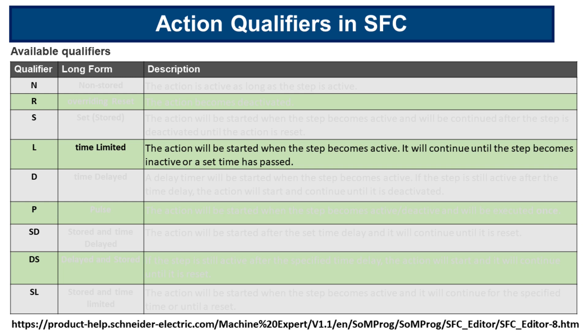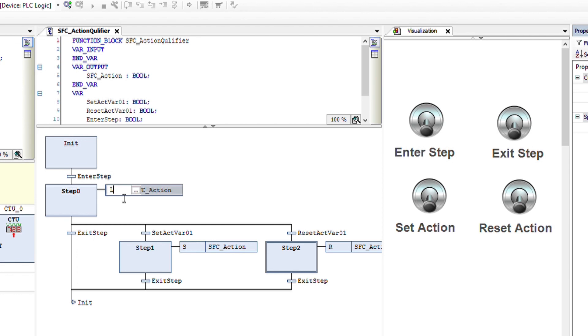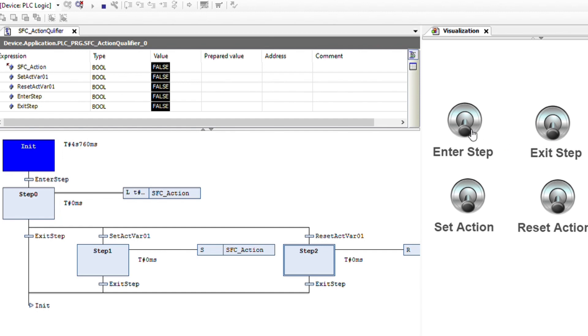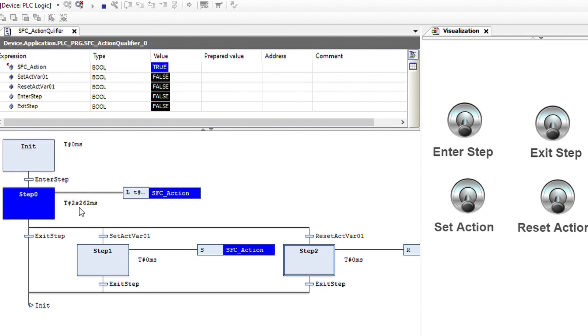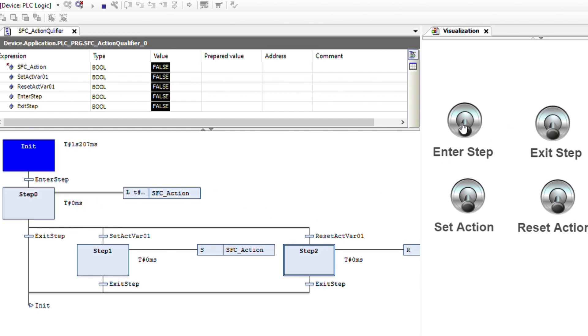The next qualifier is L, which stands for time limited. The action will be started when the step becomes active; it will continue until the step becomes inactive or a set time has passed. I'm going to change the qualifier to L and specify a time value — T#3s, three seconds. We are in the init step. If I press enter step, we enter into the step. The action becomes true and it will remain true for three seconds, then it becomes false. If I enter into the step and leave before three seconds is over, the action goes back to false.